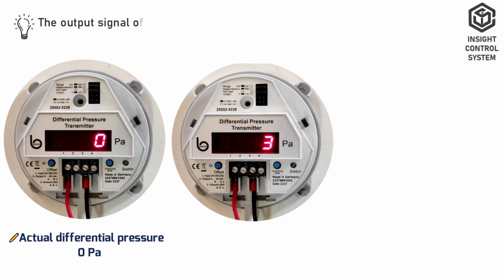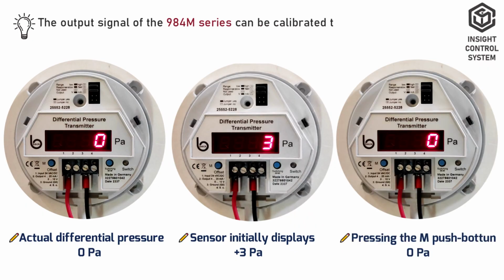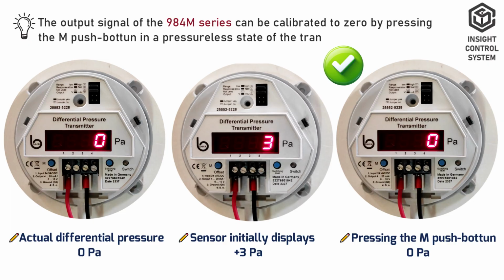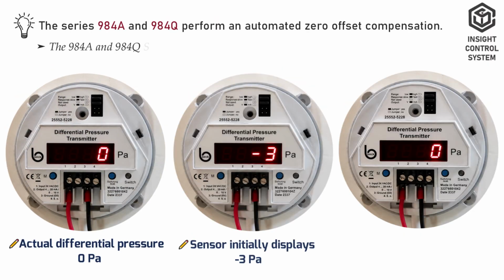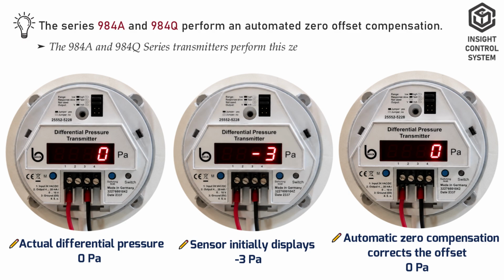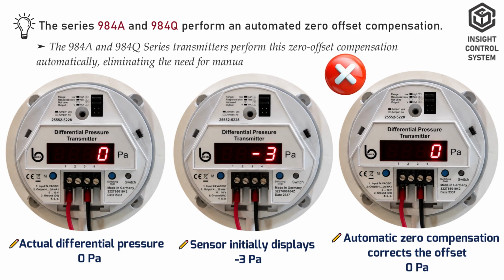The output signal of the 984M series transmitter can be zero calibrated by pressing the M push button while the transmitter is in a pressure-free condition. The 984A and 984Q series transmitters perform this zero offset compensation automatically, eliminating the need for manual calibration.